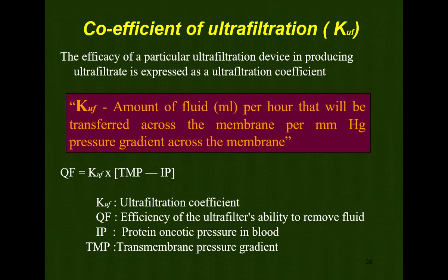Transmembrane pressure is there, negative pressure is there. But the biological system also has oncotic pressure, which is the opposition to your transmembrane pressure. Once you take all these things into account, you finally derive the coefficient of ultrafiltration. So everything is there in the coefficient of ultrafiltration: transmembrane pressure, the negative pressure of the effluent, along with the oncotic pressure. So ultrafiltration is clear.